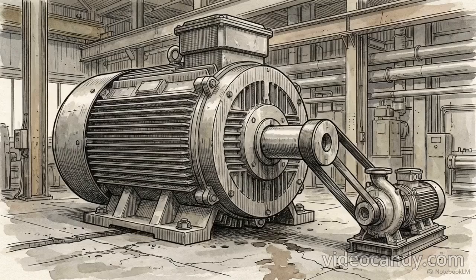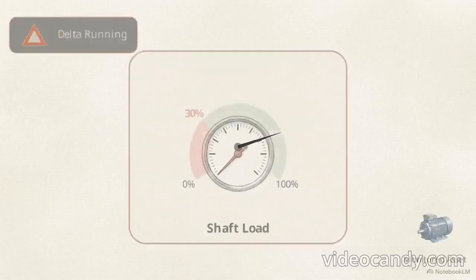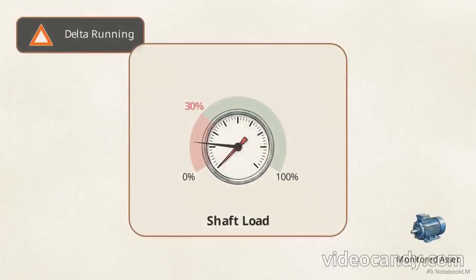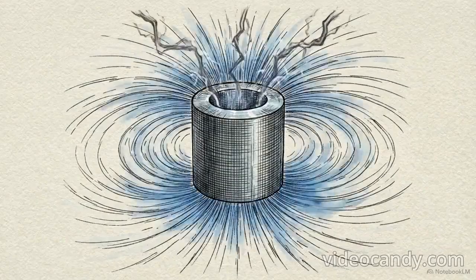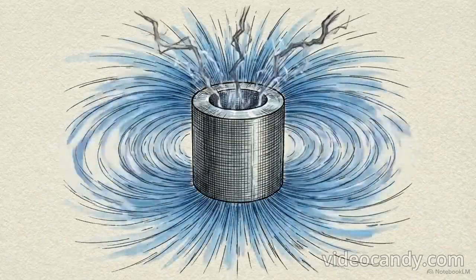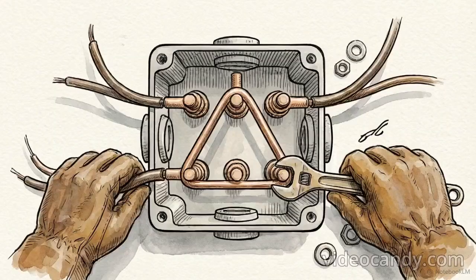Because of this heavy torque penalty, star-delta starters have a strictly defined use case. They are deployed exclusively for high inertia but low starting resistance loads, like massive industrial ventilation fans or completely unloaded water pumps. Beyond the starting sequence, the star-delta relationship can be exploited during steady-state operation to solve a common industrial problem: motors that are vastly oversized for their actual daily workloads.